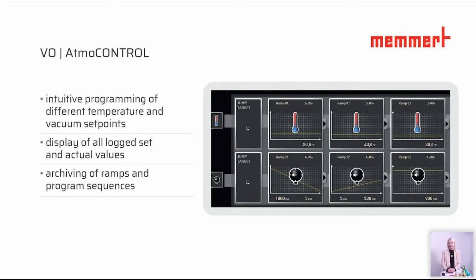For these purposes, to go down in pressure and up again and down is a very good way, because whenever you go up in pressure, it means that in short intervals, air comes into the chamber. If you go down again, it will be pulled out, and then you have a very good result for your drying process. So, with the software Atmo Control, you can do this programming very nicely.